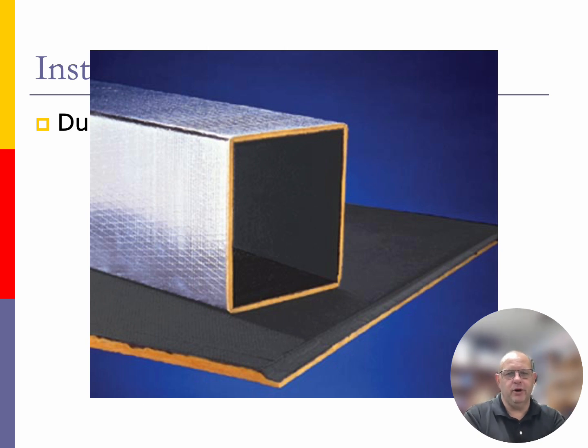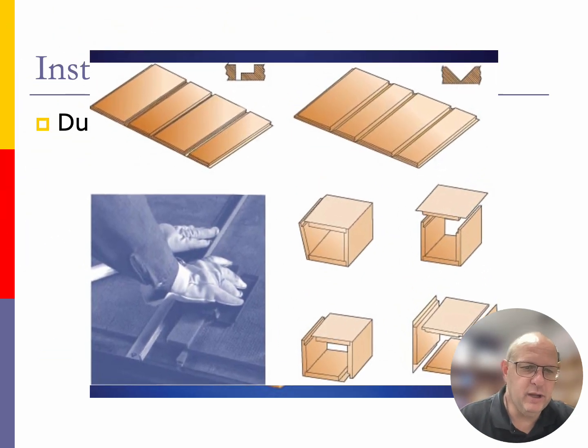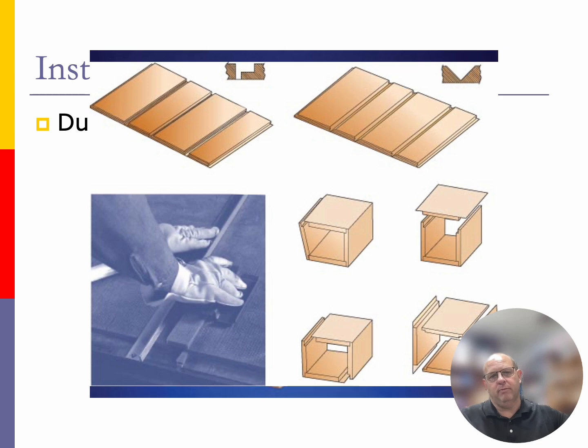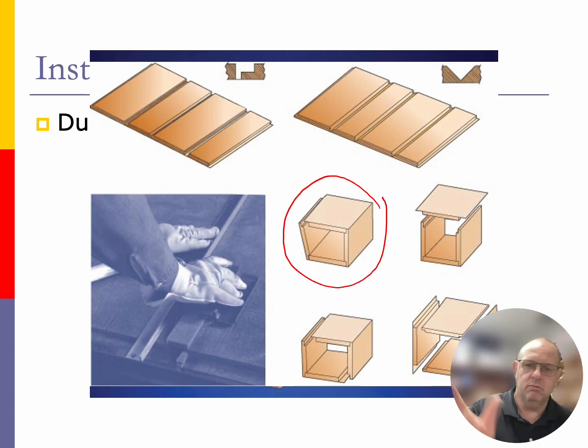So as we're talking about the ductboard on our systems, this is an example of what that ductboard is going to look like, preventing the vapor from getting into the system, the moisture. By that foil back insulation that's on there, we can see these are pressed together. We can see that we can cut grooves into this ductwork, and I'll show you that here in a little bit. That we can take this flat piece of ductboard, cut these grooves into that ductboard, and then create our square airflow ductwork out of it.